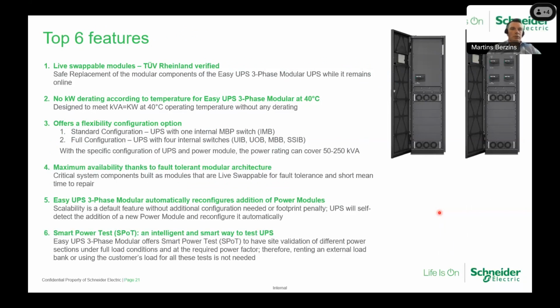So, the top 6 features which Schneider has implemented in this UPS. First of all, live swap modules. I will cover that also a bit later. But live swap means that we can safely replace the power module, static bypass, display and control module while the UPS is in the normal operation mode, basically without switching the UPS to bypass.